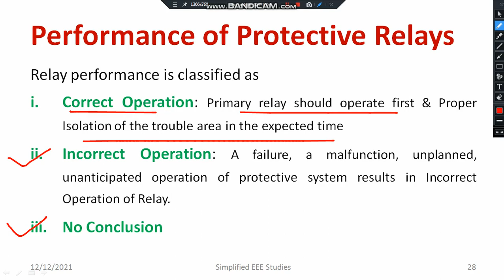Regarding performance, correct operation is needed. The primary relay operates first, and later the isolation takes place. That means first primary protection, later backup protection. In case primary protection fails, backup protection will be activated. Then incorrect operation, for example failure, malfunction, unplanned and unanticipated operation of the protective system, results in incorrect operation of a relay. That also needs to be considered. And no conclusion: sometimes no-conclusion outcomes also happen in a protective system.